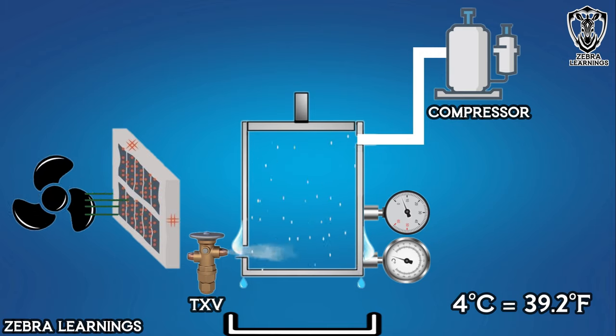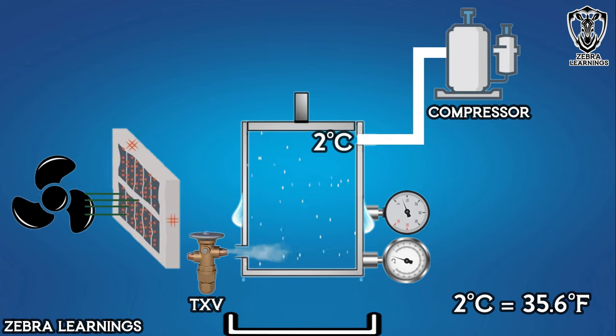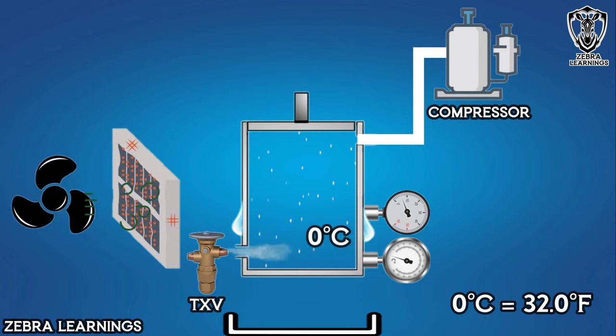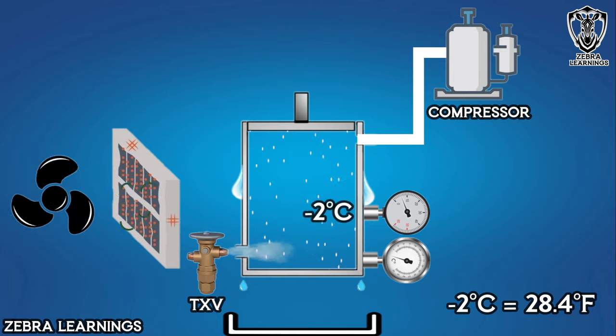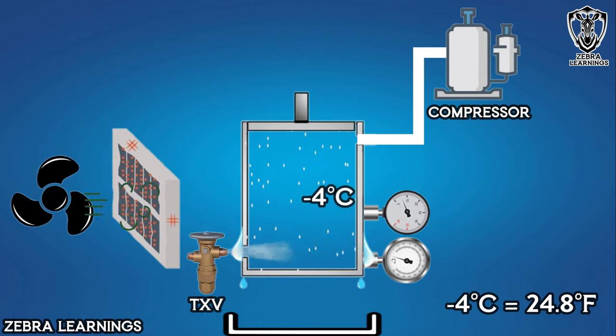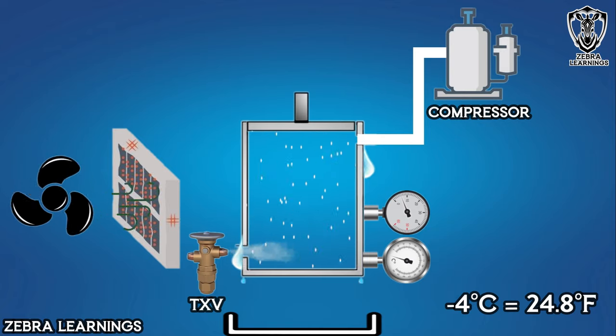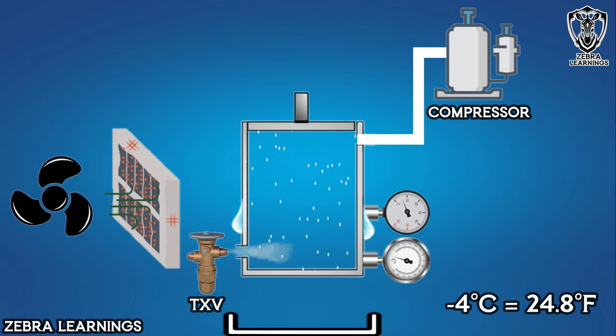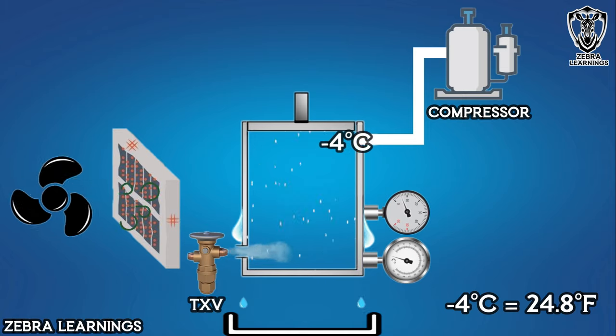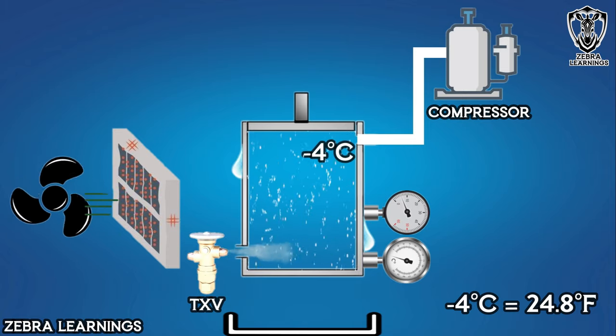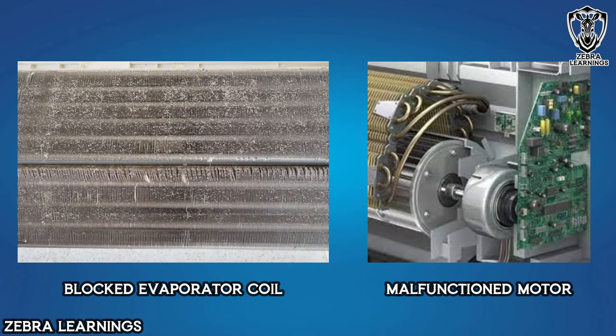As this continues, the temperature of the refrigerant coming from the expansion valve decreases, and enters the evaporator coil at minus temperature. When the temperature of the evaporator coil goes to minus, as we have already said, the water freezes and forms ice all over the evaporator coil. In the same concept, if the evaporator coil is blocked, or the blower fan is not working, air cannot flow, so the temperature of refrigerant will decrease and the evaporator coil will freeze.